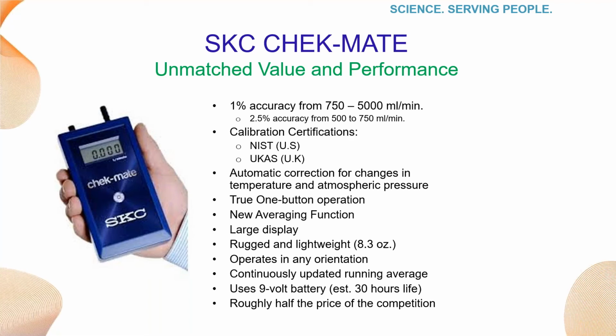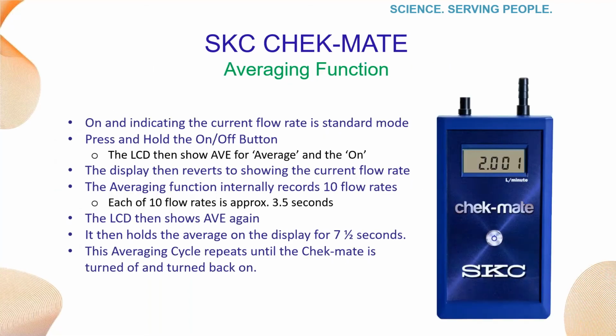I want to show real quick, and I've run out of time, the SKC Chek-mate has an averaging feature now. For some people, using the 10 cycles or multiple cycles of something is important. The Chek-mate now does have an averaging feature where you can press and hold the button, and it will indicate that it's going into the average mode. It'll tell you that it's on, and it'll then exhibit the regular flow rate as it is, and after it takes 10 flow rates of approximately 3.5 seconds, it will then exhibit average again and display the average flow rate. And then it will continue doing that until you either turn it off or restart it.